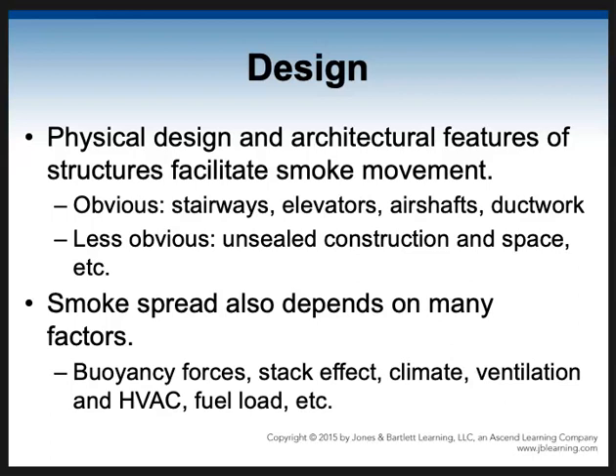So stairways, elevators, air shafts, ductworks, these are obvious places where we need to have some kind of a smoke control system, and atriums. But the less obvious, we want to also make sure where we've cut holes in the wall, we need to seal that. Unsealed construction can be a place where smoke can go from one part of the building. So there's things like that where we want to design it so it can't do that. Wherever we run utilities from one floor to the next, they cut these big holes. Well, they need to seal that.